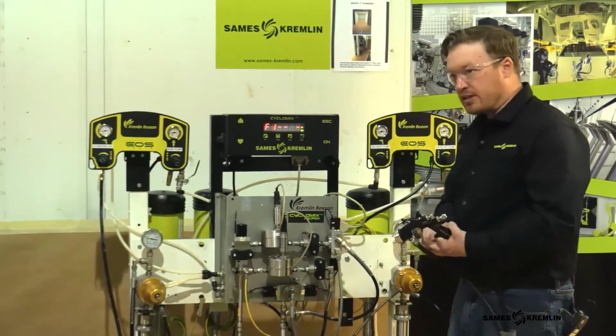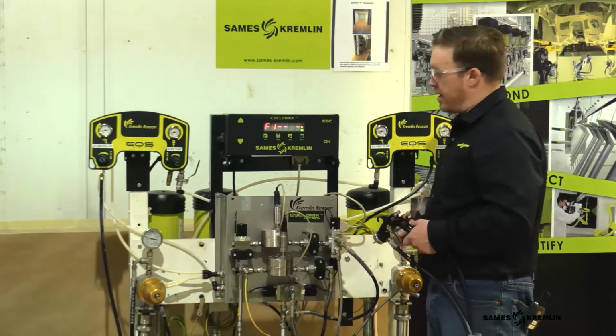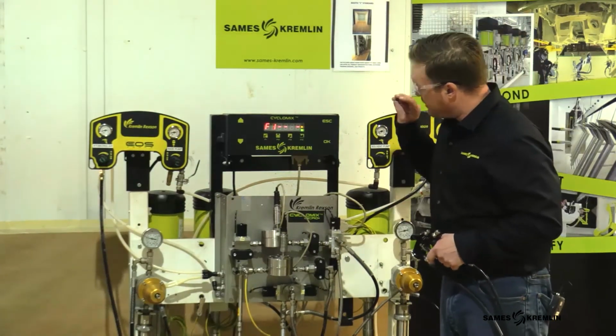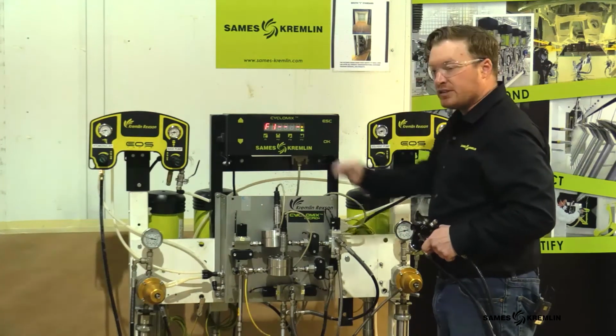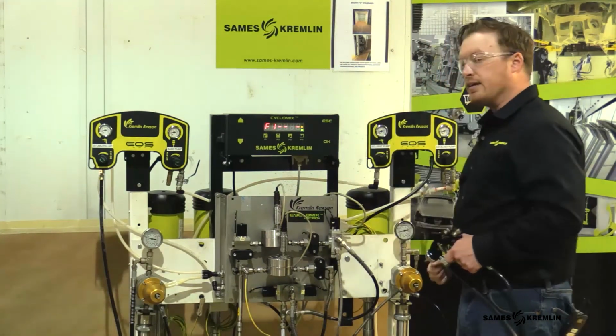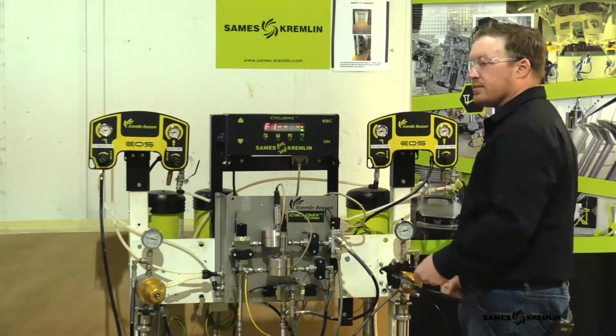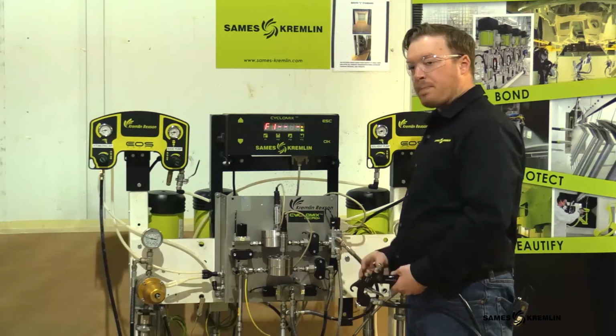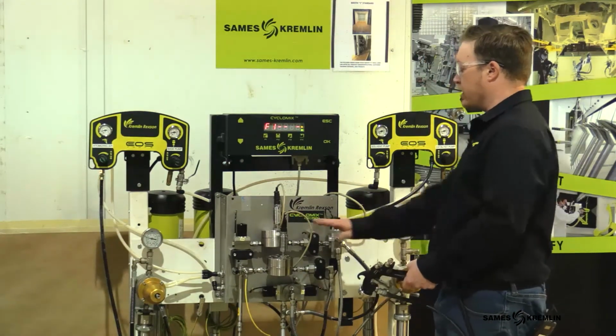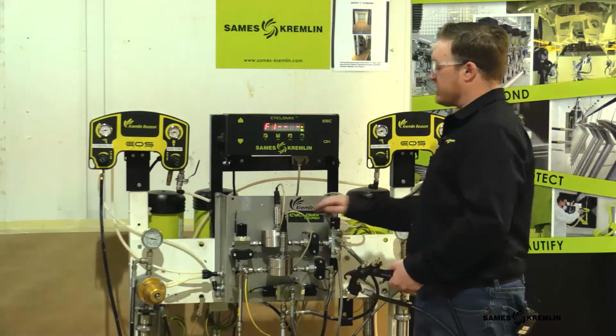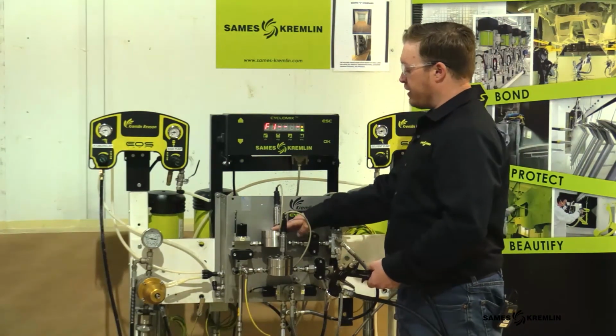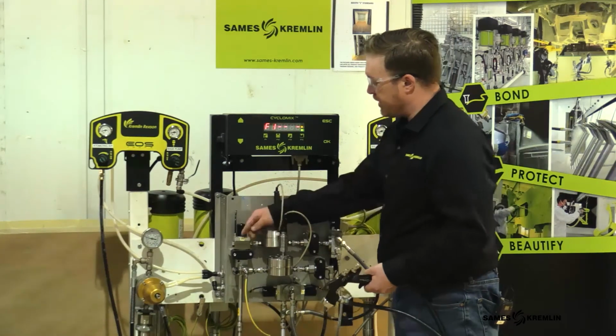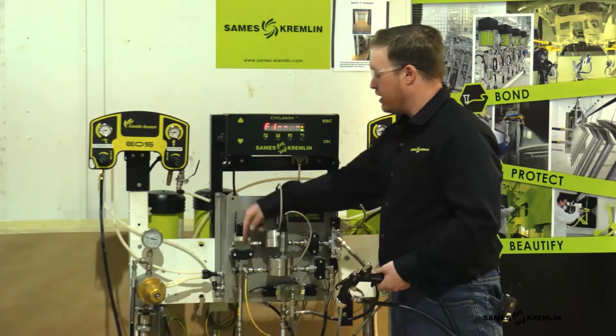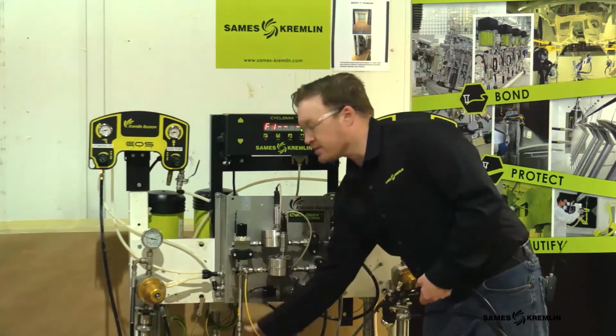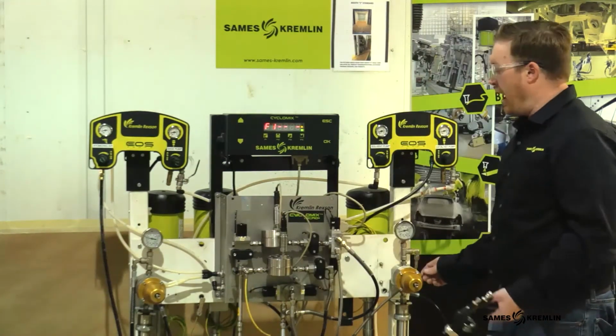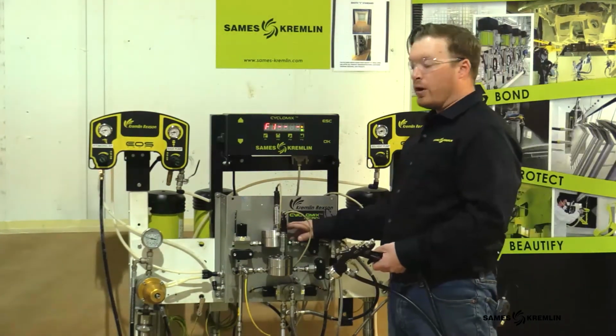So what we do, and sometimes it can be a little bit of a process, is you simply continue to reset and reset and reset until that air balances out. And what is happening is we're compressing that air into the gear, the flow meters, and pushing it through the VP6. And once it's through the VP6 and into the static mixer, it's fine, and that error 5 will go away.